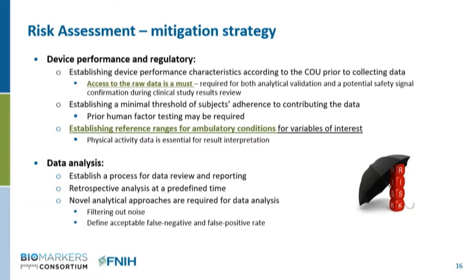Access to raw data is essential and serves two purposes: first, to verify that the concept being measured is captured accurately; and also for verification if there is a safety signal. Prior human factor testing is required because if a device is not convenient or difficult to manage by study subjects, there will be missing data. Interpretation of ambulatory data is far more challenging than the resting and supine protocol. For data analysis, there is a need for data review and reporting, novel analytical approaches that include filtering out noise, and defining acceptable false positive and false negative rates to find the right balance.